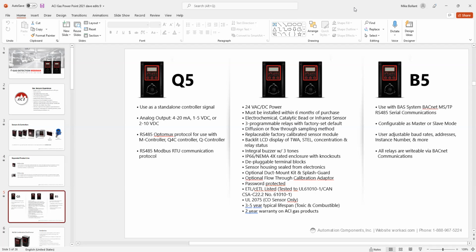The Q5s and the B5s, basically, here's the differences. Q5 is, of course, the analog version. You can do it standalone, or you can daisy chain them via the RS-485. Like I said, you can do up to 32 on the M controller, 128 on the Q controller, depending on the size of the job. And you can mix and match the sensors. It doesn't matter if it's CO, NO2, methane, hydrogen, oxygen. That all comes down into the programming on the software, which is included in our programs.